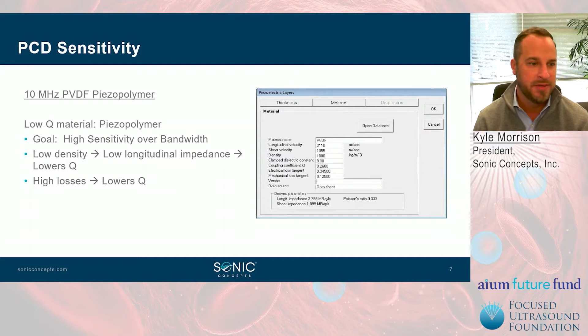All right, so we have different kinds of PCDs. Let's talk about the wide passband version. This is a 10 megahertz PVDF piezo polymer material that I'm going to be discussing. It has a low Q. Its goal is to have a reasonably high sensitivity over a large bandwidth. And then we really want a low density material, which this is, with a low longitudinal impedance, which lowers the Q, and then high losses, which lower the Q. And then in combination with the piezoelectric layer, we use front matching layers and rear acoustic loading materials used to optimize the sensitivity over the bandwidth.